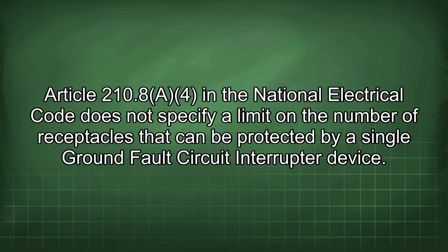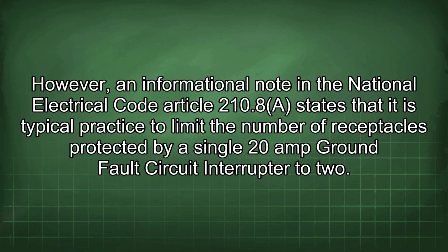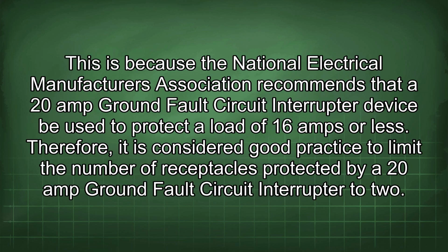Article 210.8 in the National Electrical Code does not specify a limit on the number of receptacles that can be protected by a single ground fault circuit interrupter device. However, an informational note in the National Electrical Code Article 210.8 states that it is typical practice to limit the number of receptacles protected by a single 20-amp ground fault circuit interrupter to 2. This is because the National Electrical Manufacturers Association recommends that a 20-amp ground fault circuit interrupter device be used to protect a load of 16 amps or less.